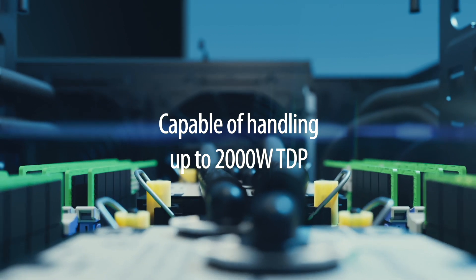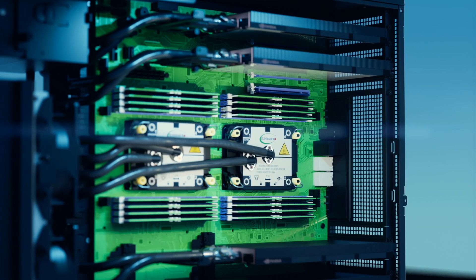We are extremely excited about this closed-loop liquid cooling technology built for both CPUs and GPUs, capable of handling up to 2000 watt TDP. The liquid cooling works by distributing liquid from an internal reservoir to the two CPUs and four GPUs in the system through two high-performance pumps.